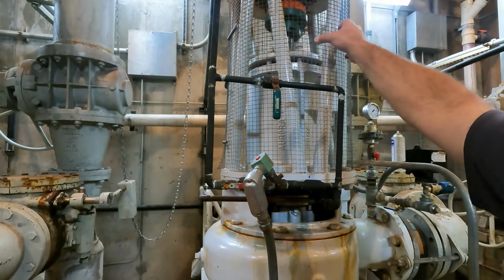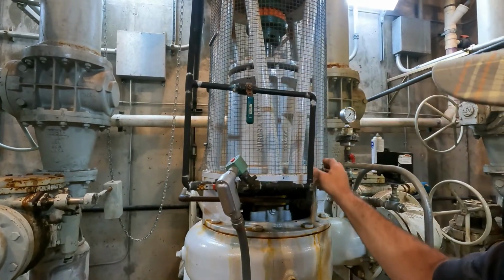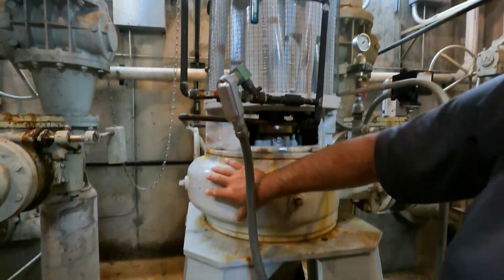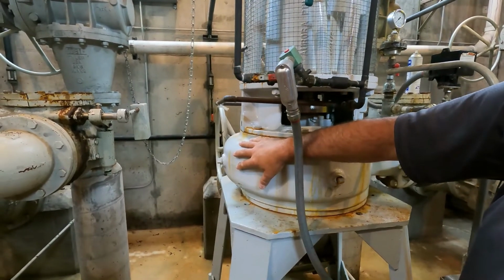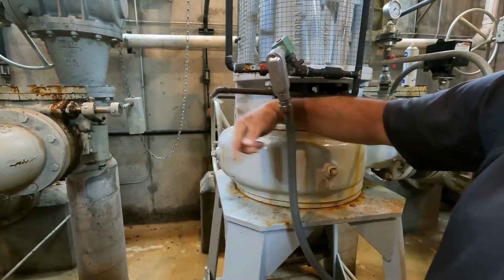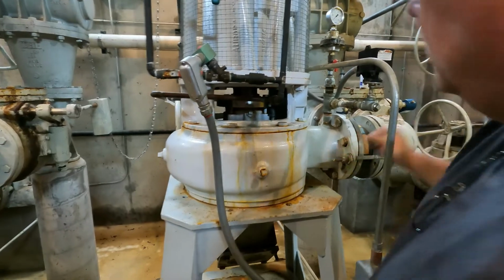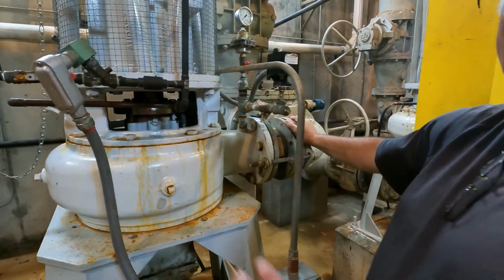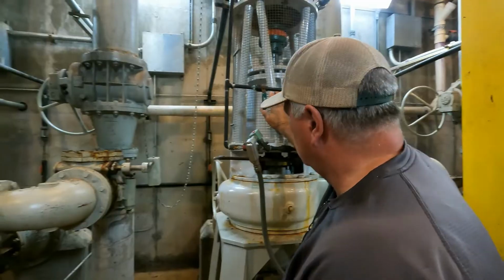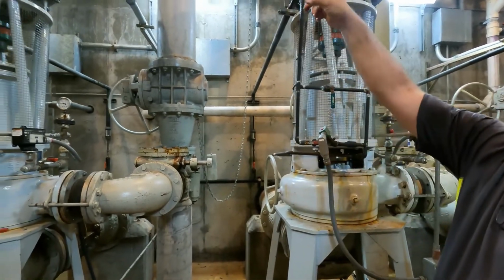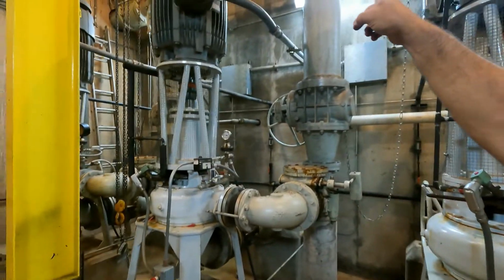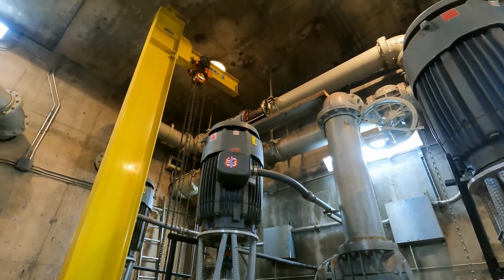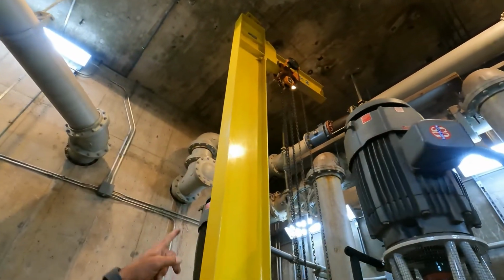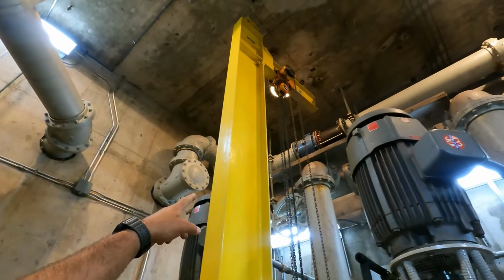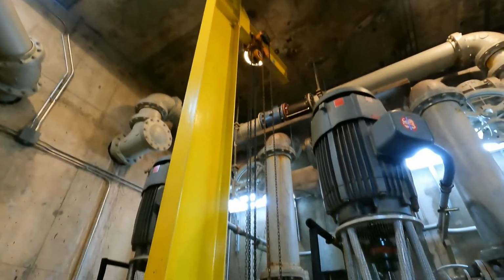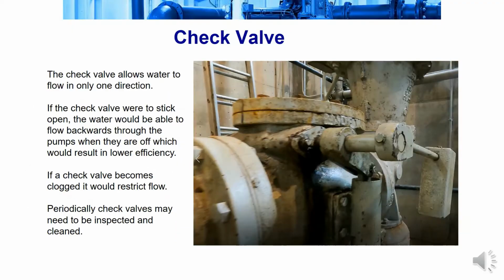And then so the main motor would drive the pump down into the impeller inside of the volute. The impeller is spinning at a centrifugal motion to throw the water to the outside of the volute that forces it up through the check valve and out to the plant. We got up on top of there, you can see the actual mag meter, flow meter. Where the water is going through that is what is actually being measured up on the circular chart.